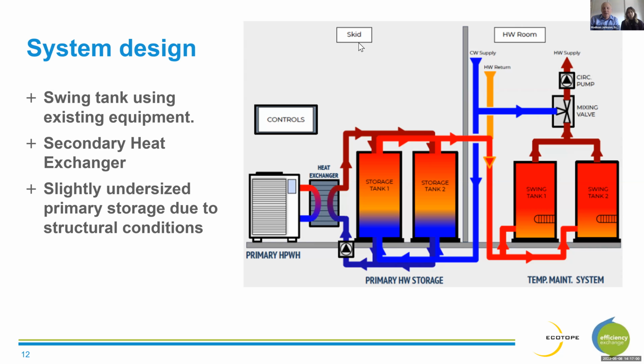And the difference of the Mitsubishi product to most of the products that are on the market right now is that secondary heat exchanger, so that the potable water is not going directly through the heat pump, but it's separated by a heat exchanger. This allows Mitsubishi to protect their coil from any water quality issues and scaling, and also allows them to put some freeze protect chemicals in that loop if needed. We didn't do that in the city of Seattle, but in colder climates, they may do that.